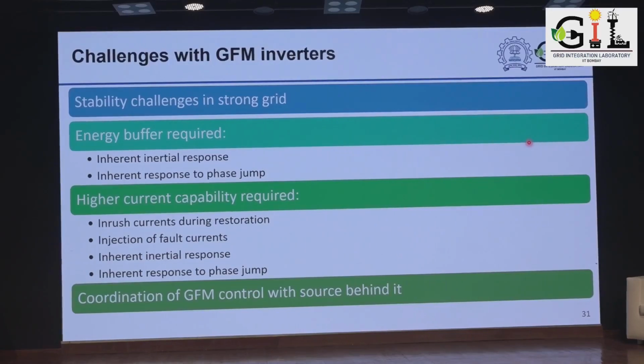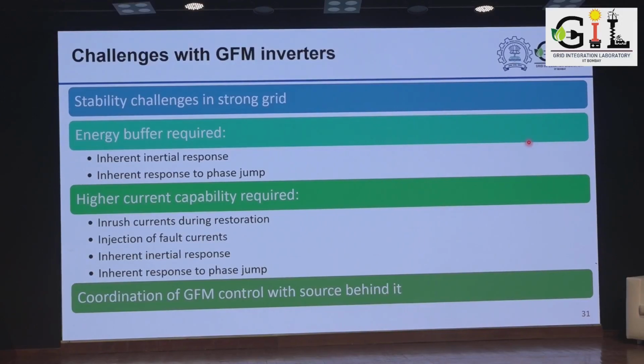Grid forming IBRs are expected to strengthen the grid. So the low short circuit ratio issue can be, to some extent, addressed through this grid forming converter technology, which is technically very correct. But in high strength grids, grids with high SCR ratio, there have been instances where it has come out that grid forming technology actually has a detrimental impact when the SCR is high.